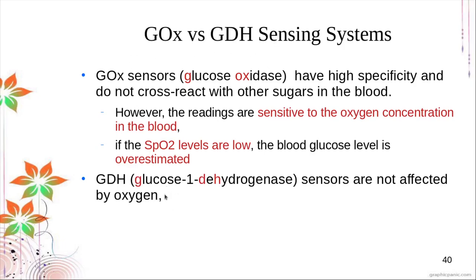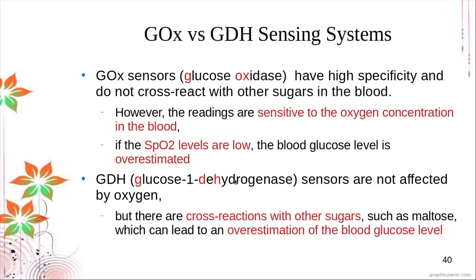The other system is GDH, glucose dehydrogenase. GDH is not affected by oxygen concentration at all. However, GDH is not very specific to glucose. In your blood, glucose is not the only sugar — you also have maltose and lactose. GDH can also react with maltose, so if you have high maltose concentration, the GDH system will detect maltose and read it as glucose, tending to overestimate blood glucose levels.